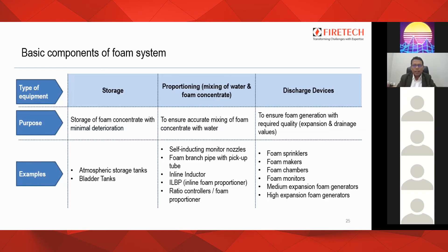The last component is discharge devices, which convert the foam solution into finished foam — the foam applied on the fuel surface. Their purpose is to ensure foam generation with the required quality, which consists of two parameters: expansion and drainage. Examples of discharge devices include foam sprinklers, foam makers, foam chambers, foam monitors, medium expansion foam generators, and high expansion foam generators.